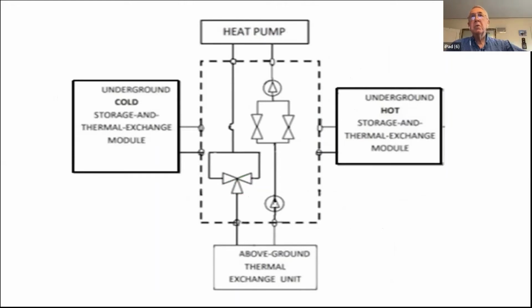So when we go to the air source mode, the connections and the flow are as shown in this graph. Neither of the ground loops are in operation, or in use, I should say. We have the flow equal from the two water pumps. So it's counterclockwise. The arrow indicates direction of flow, actually. So we have water flow coming up this way, coming down this way, and these two valves are set. So we do not allow any flow horizontally into this block or the left-hand block.